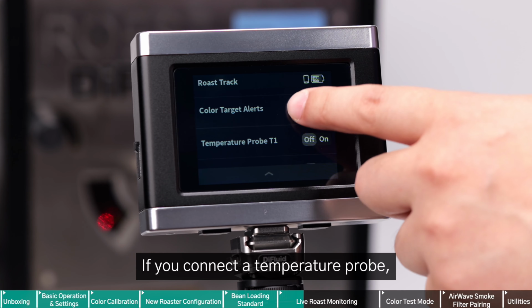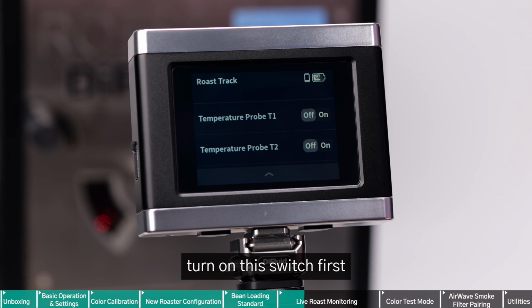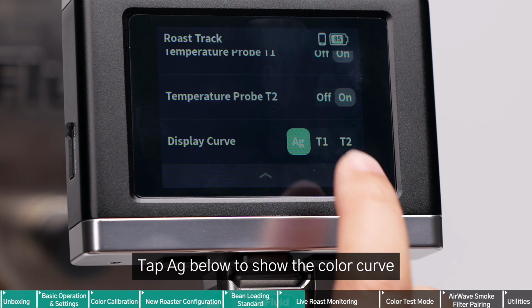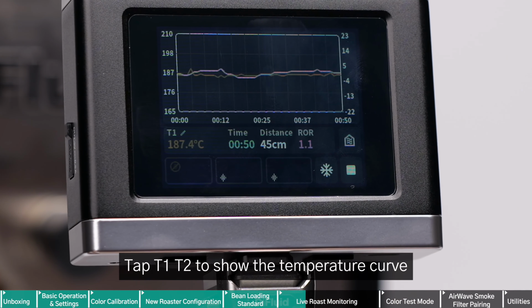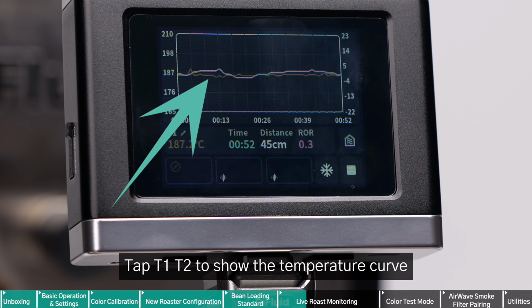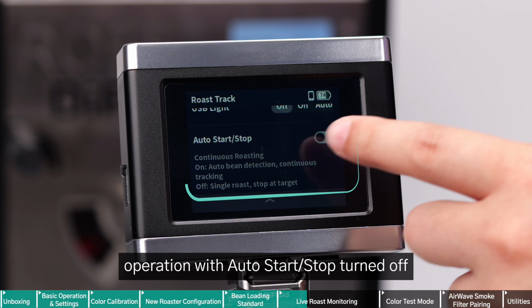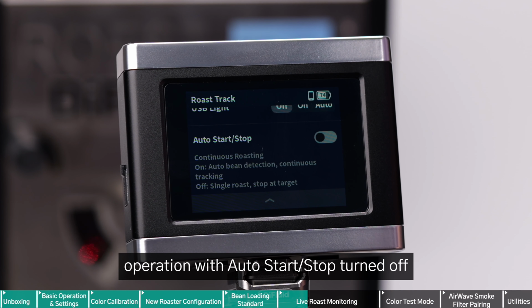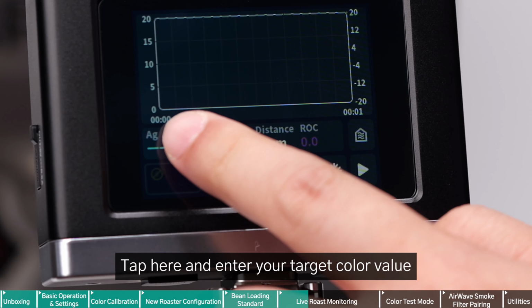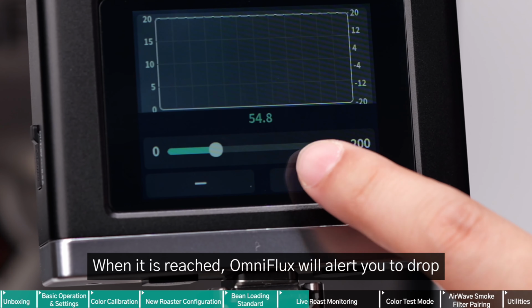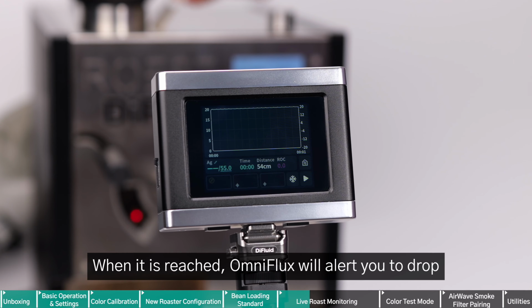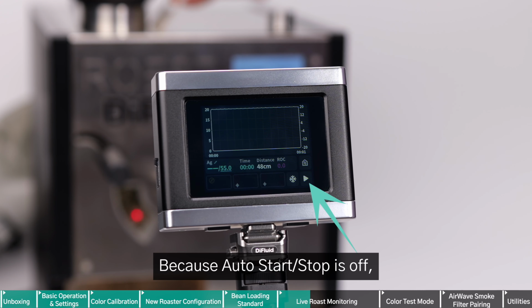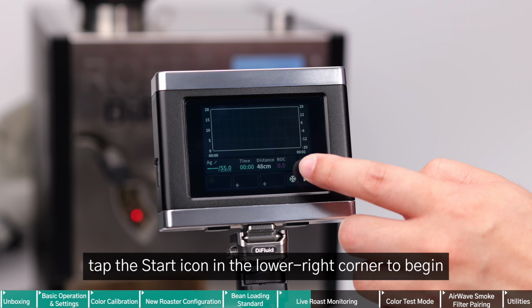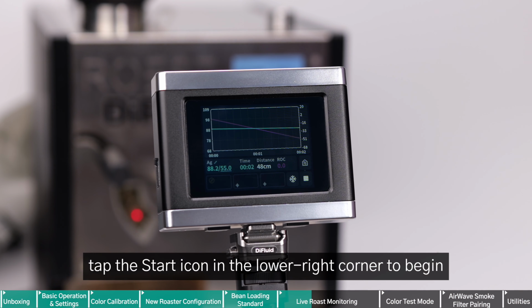If you connect a temperature probe, turn on this switch first. Tap Ag below to show the color curve. Tap T1, T2 to show the temperature curve. We will now demonstrate operation with the Auto Start Stop turned off. Tap here and enter your target color value. When it is reached, OmniFlux will alert you to drop. Because Auto Start Stop is off, manually tap the start icon on the lower right corner to begin.